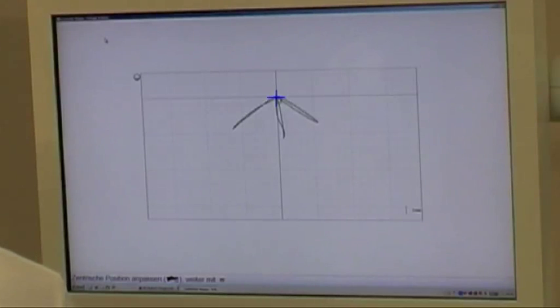To do this I restart the module and see on the monitor the actual position of the support pin as a green circle. If the centre of this circle is on the desired centric position the measurement is ended. This will fix the centric position electronically.